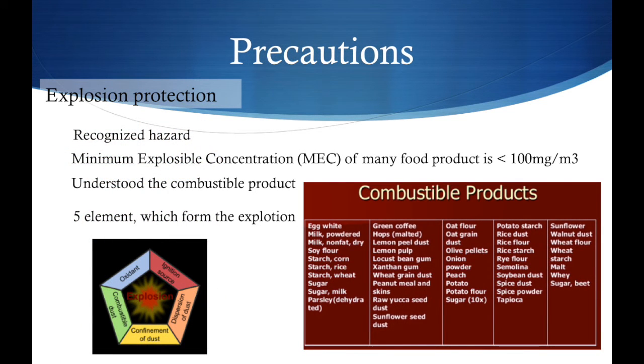There is also a hazard when using the spray dryer. The most common one is dust explosion. The minimum explosible concentration of many food products is less than 100 mg per cubic meter. There are five elements contributing to an explosion: oxidant, ignition source, dispersion of dust, confinement of dust, and combustible dust. Examples of combustible products are egg white, milk, green coffee, potato starch, walnut dust, wheat flour, and many more.